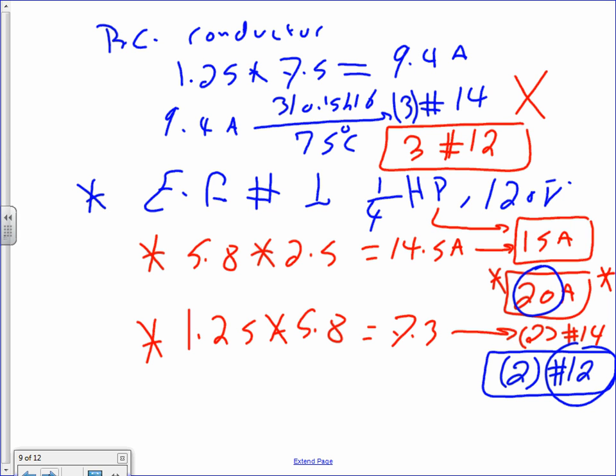Remember, these are single phase. And 1.25 gets you 7.3, number 14. So a 15 amp breaker, number 14. Here's where I use my judgment. What did we say we don't want to use? We don't want to use number 14 conductor, and we don't want to use a 15 amp circuit. So this is judgment. I up this to a 20 amp circuit, because I know this pump most likely has an overcurrent protection device anyway. So I put a 20 amp circuit and I feed it with number 12. Why 12? I don't want to use number 14. It's not a good idea. Can I have thumbs up, Chad? That's how we do that. Here's your other example for single phase motors.